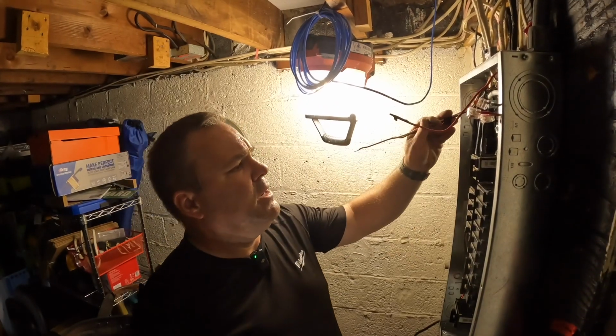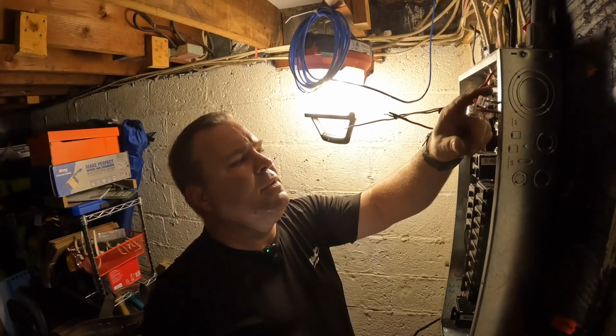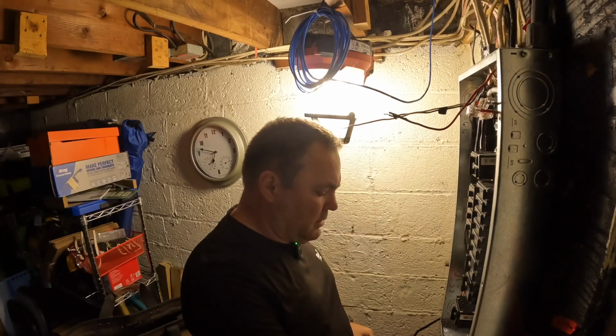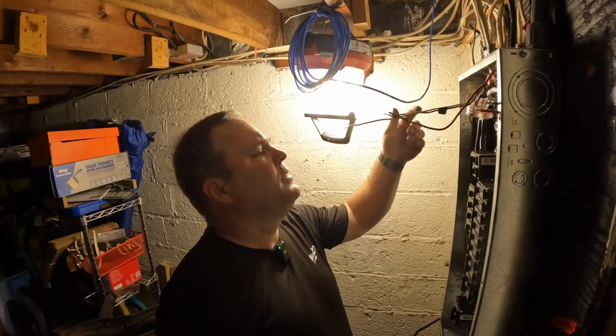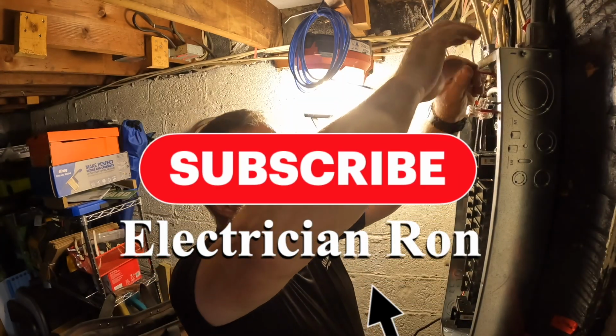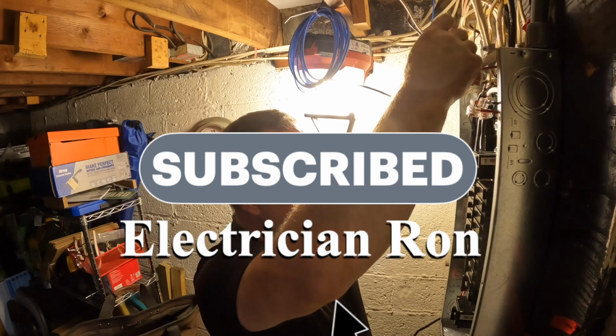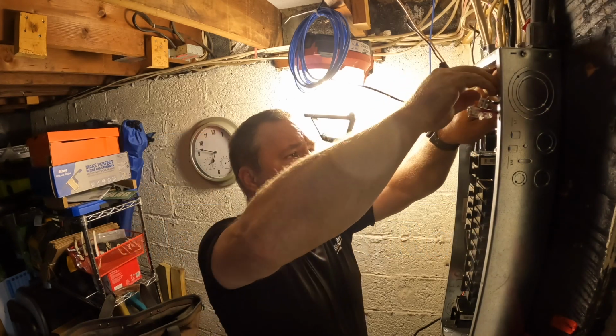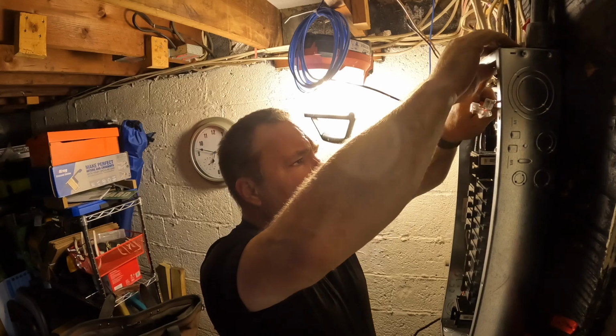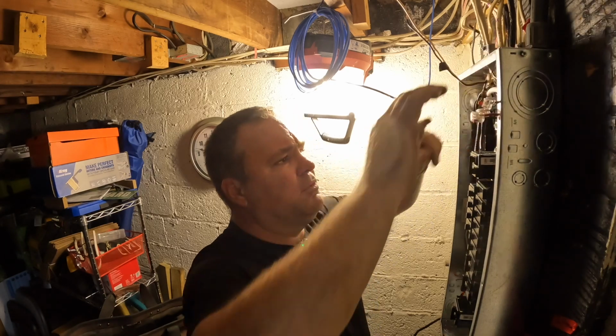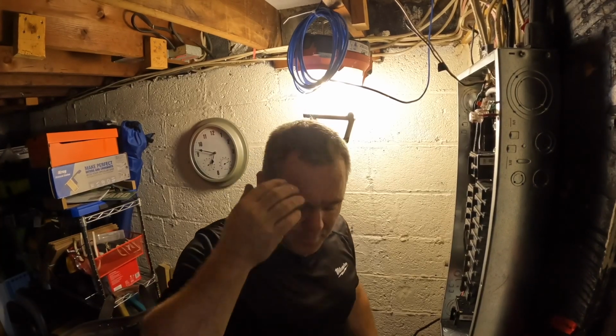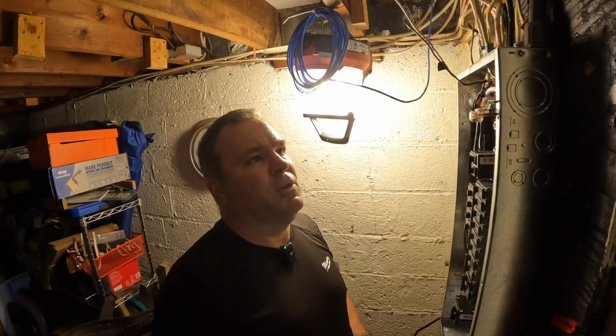Oh, I got to get the GFCI breaker here, and I need to do the condensing unit wiring. I got about 10 minutes to get that done before my 3 o'clock deadline that I promised my customers that the power will be back on, being that this was just only a panel change only. So I can get done a little bit early. Had this been a full upgrade, I would have come here the day before and done the grounding system so that I could be ahead of the game, so the power will be off less than if I wasn't there the day before doing advanced work.